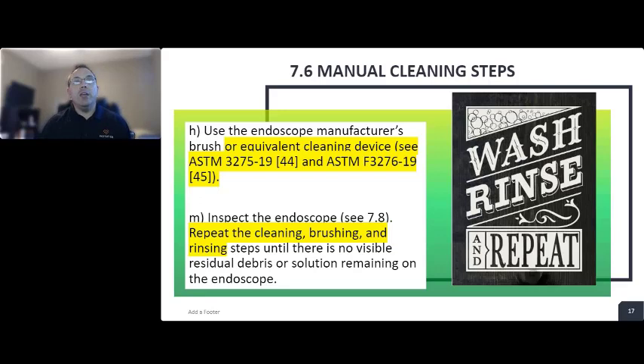Now, the other big thing here is wash, rinse, and repeat. I love this piece of it. Use the endoscope manufacturer's brush or an equivalent cleaning device. And then it shows us a standard here in ST91. I've worked with many, many brush manufacturers around the world. Brushes are not just manufactured in the United States. They're manufactured all over the world. And so this standard that is in here, I have an issue with it. There's nobody that follows it in the brush manufacturing world. It doesn't exist in their terminology. The other side is there's nobody to monitor that. So the manufacturers don't use this standard. If you're not using a standard and the standard is not proven out in any way, how are we referencing it?